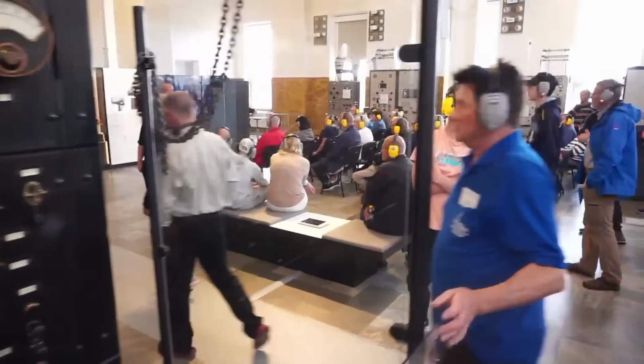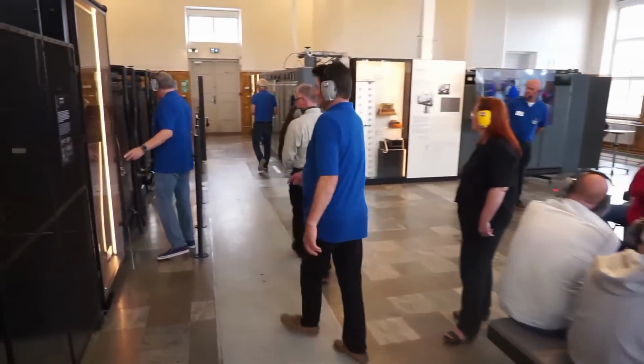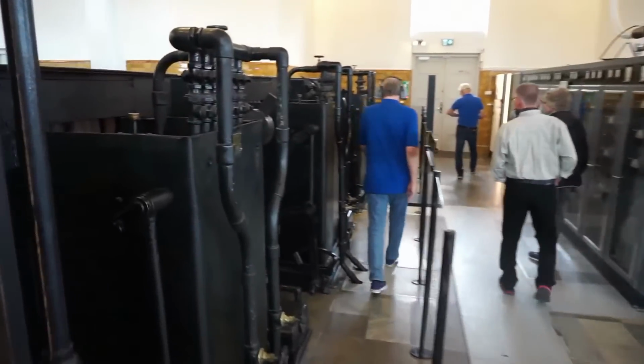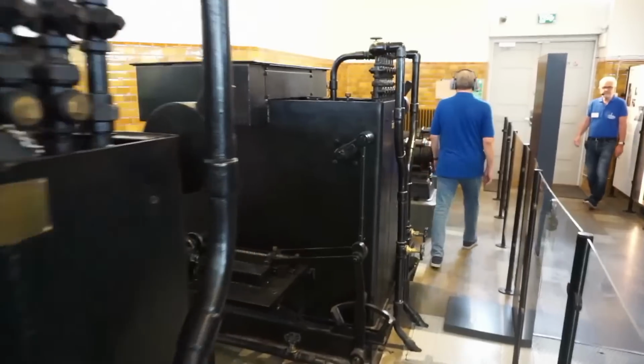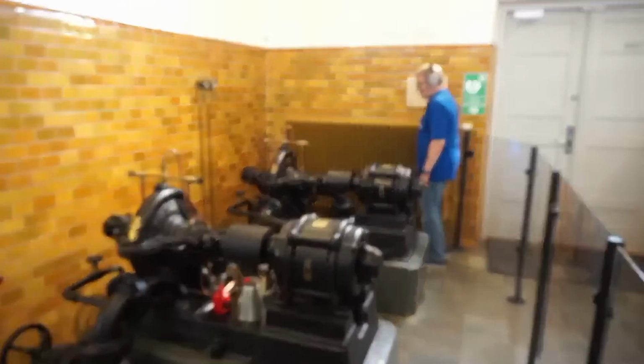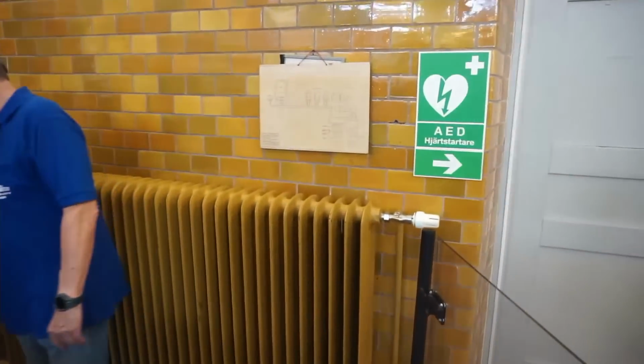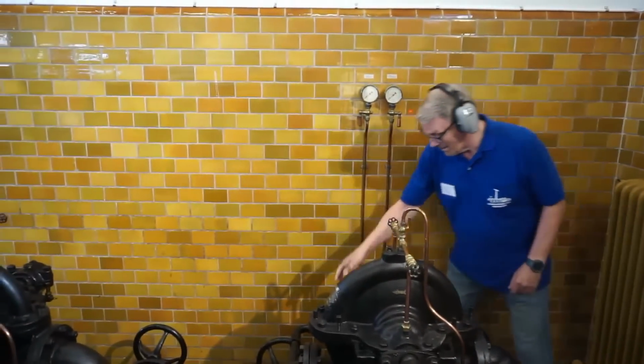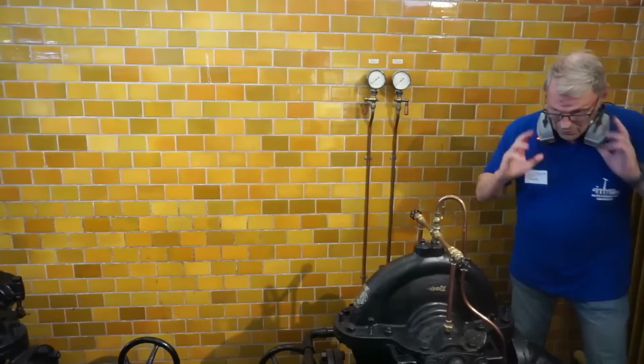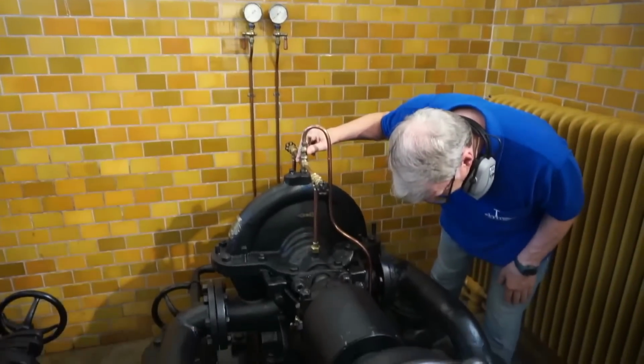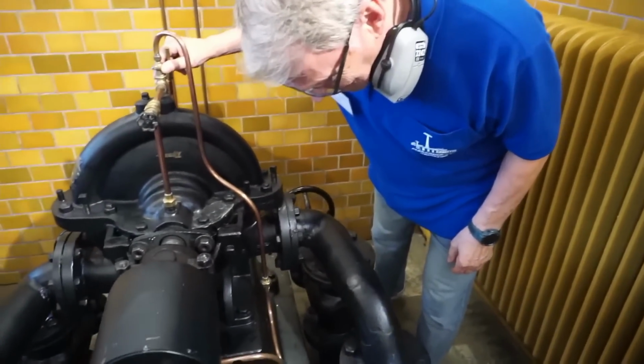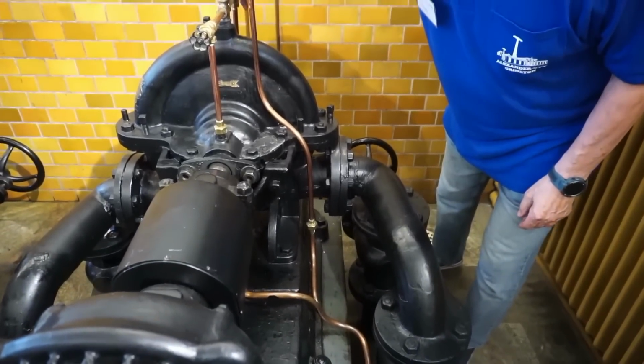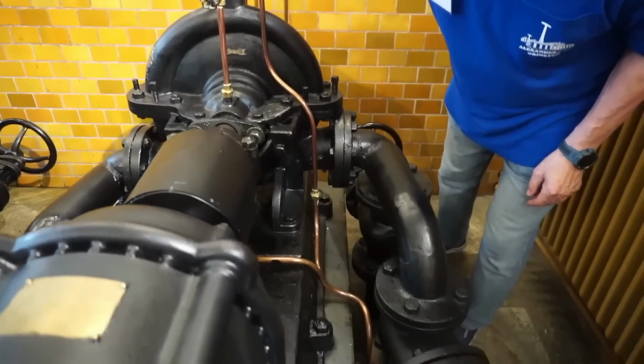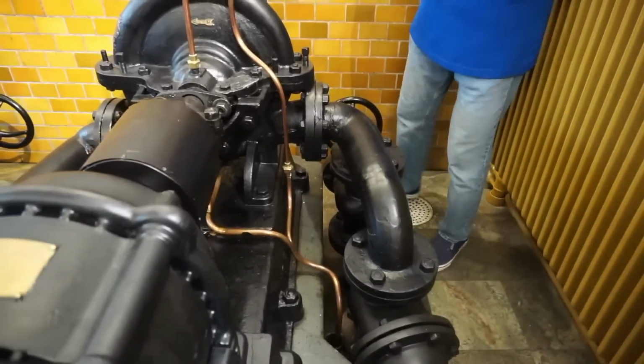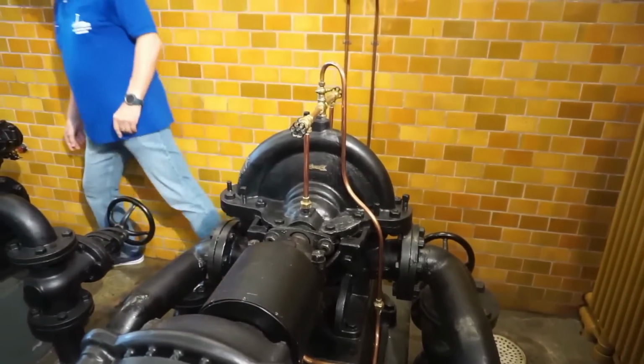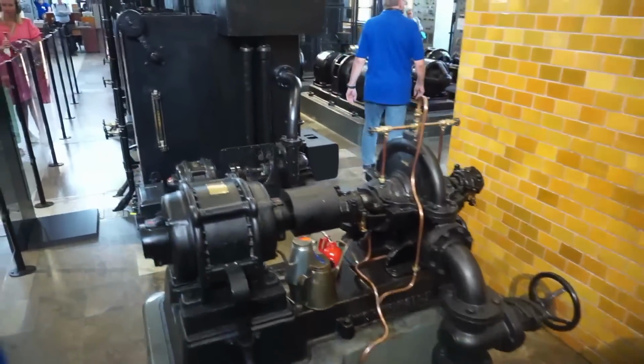Now we are going down to start up the cooling water system. We have 2 centrifugal pumps down here. And we will use pump number 2. The other is a backup. Jan-Åke starts up by opening a bleeding valve to get rid of air pockets in the pump house. He's listening. At the drainage pipe, there will be only pure water coming up. He switches off the bleeding valve and starts up the pump with a star delta switch.